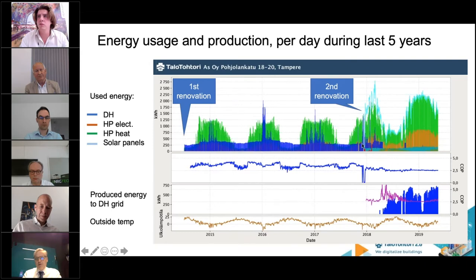And then the second renovation happened 1.5 years ago. That was the phase when all this new equipment was installed. We can see here that in the springtime of 2018, the building started to sell energy back to the grid. The sold energy amount is this third graph here, showing blue bars. And the lowest graph is the average outside temperature. So we can see that a few months after the second renovation, when the system was up and running properly, the building almost completely stopped consuming district heating. It gets all the energy needed locally on site, and also sells the excess heat back to the grid.